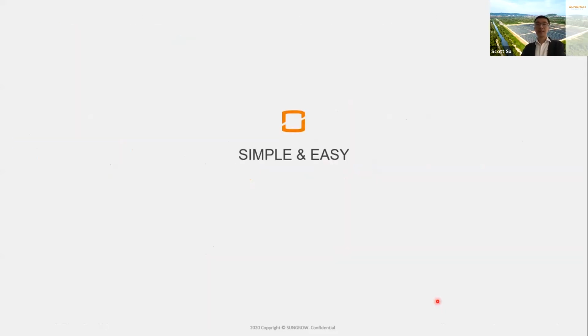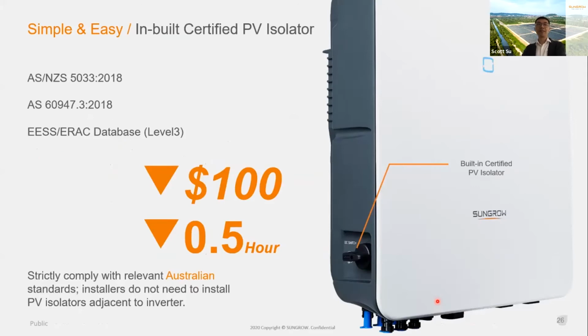Okay. The next section is very simple and very easy. Firstly, we have these inbuilt DC isolators, and this DC isolator can comply with all relevant standards in Australia, such as AS5033, the installation standard. Second, this DC isolator has the local certificate, AS60947 Part 3. Thirdly, this DC isolator has already been listed on the Electrical Regulatory Authorities Council, ERAC, and the category is level 3, so no need for external DC isolators anymore. This design can save you $100 and half an hour of installation time.